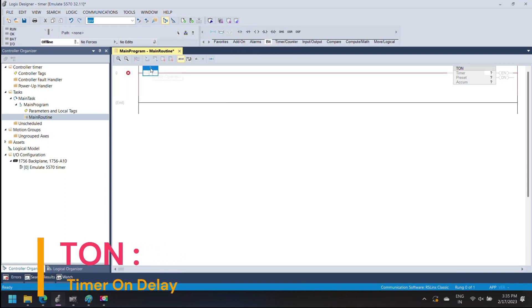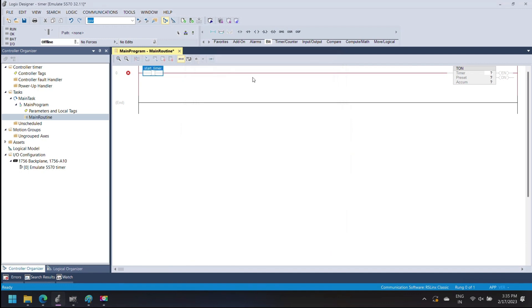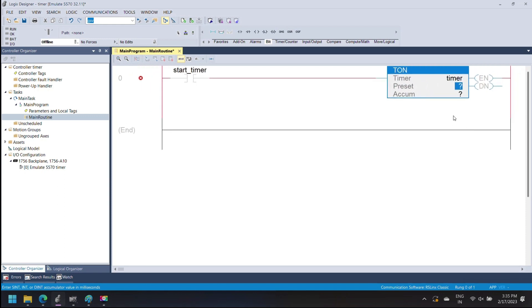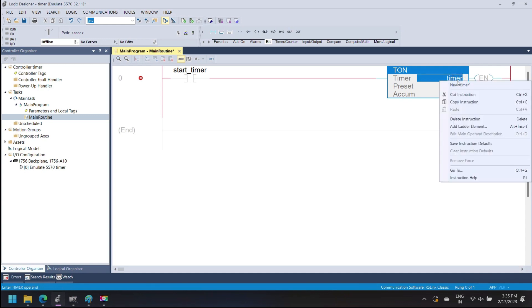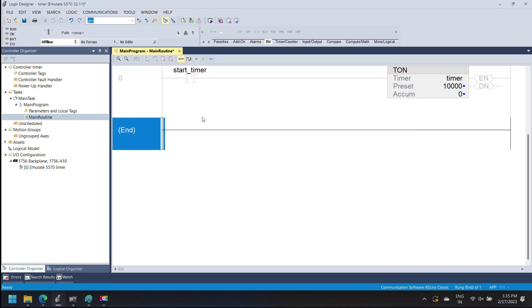Timer On Delay starts when the input bit of the timer is set to true, and runs until it reaches the preset value. The base of the preset value is 1 millisecond. If you want to run your timer for 5 seconds, the preset value is 5,000. The accumulator value accumulates the timer value. When the timer accumulator value is equal to or greater than the preset value, the timer stops running and the timer done bit is set to true. Now I am adding a timer instruction with a 10,000 millisecond preset value, which is equal to 10 seconds.